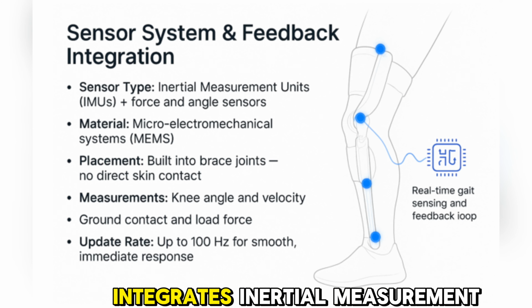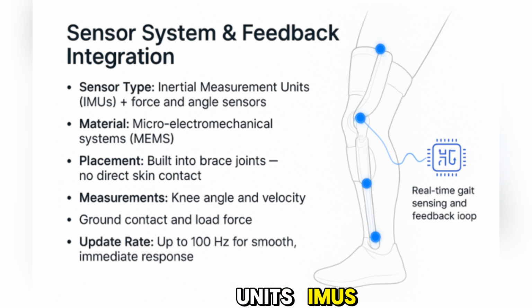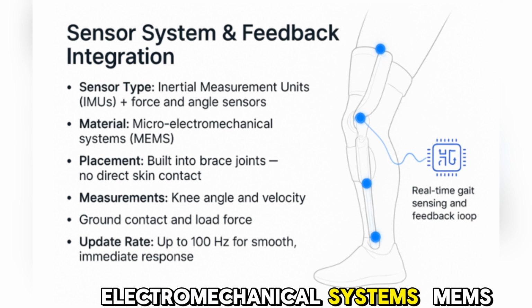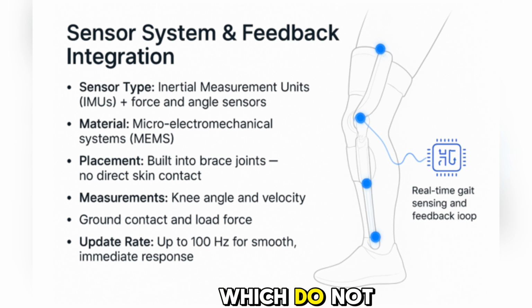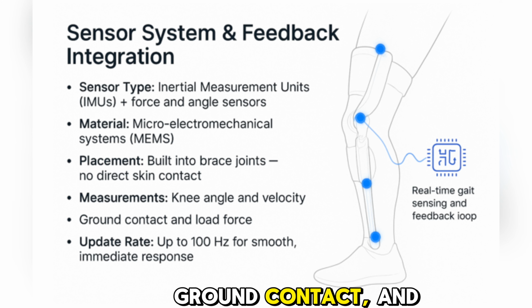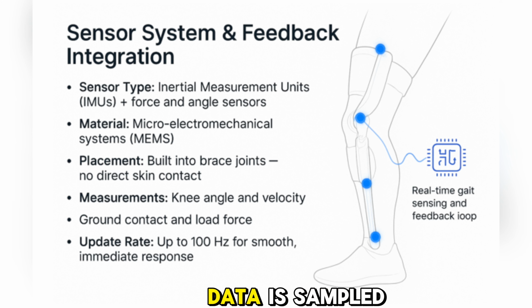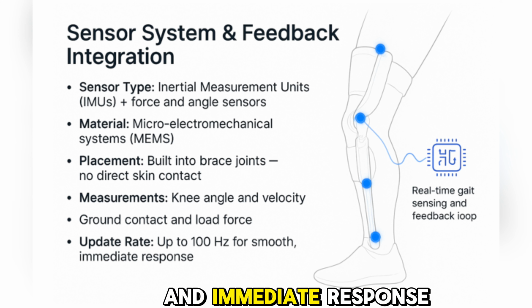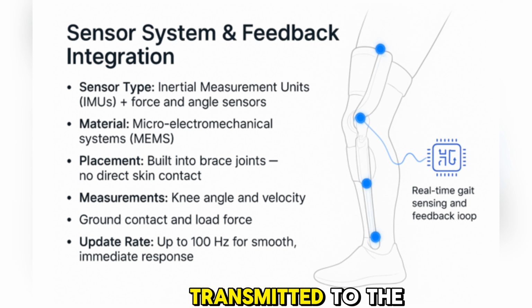The sensor system integrates inertial measurement units, IMUs, force sensors, and angle sensors that are embedded within the brace joints. These are micro-electromechanical systems, MEMS components, which do not require direct skin contact. The sensors measure knee angle, angular velocity, ground contact, and load force. Data is sampled at update rates up to 100 Hz, providing a smooth and immediate response. This information is transmitted to the microprocessor in real time, forming the input layer of the closed-loop control system.